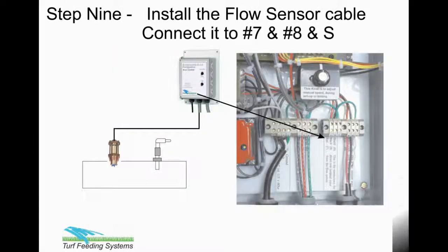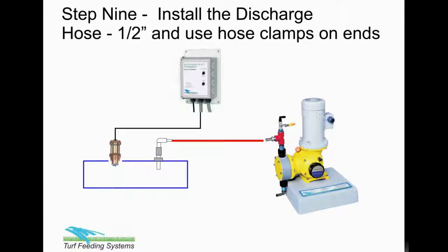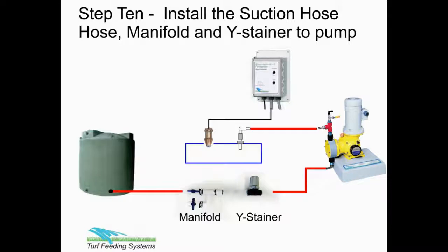Next, install the flow sensor cable wire to the controller: red to number 7, black to number 8, and shield to S. Next, install the discharge hose, 1/2-inch red hose from the injection valve to the pump discharge fitting, top valve on pump head. Secure the hose with the small hose clamps. Next, install the suction hose from the tank to the suction manifold and to the Y strainer and then to the pump suction fitting. Use hose clamps on all hose connections.